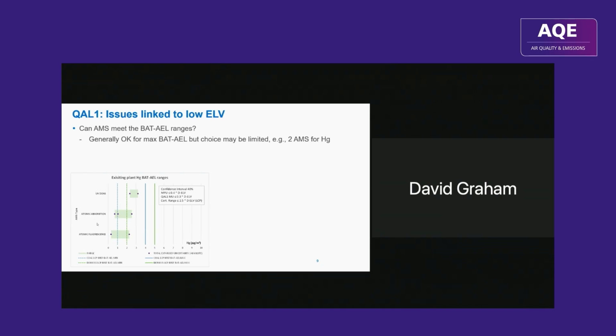So you can see on the y-axis 3 different principles of mercury analysis, fluorescence, absorption, and so on. And then the purple dots are the measurement, the expanded uncertainty from the certificate in each case in microgram per meter cubed. And then the vertical lines represent the BAT-AEL ranges. So for coal, for example, the range is from 1 to 4 microgram per meter cubed for existing plant. You can see in the box that the confidence interval for mercury is 40%.